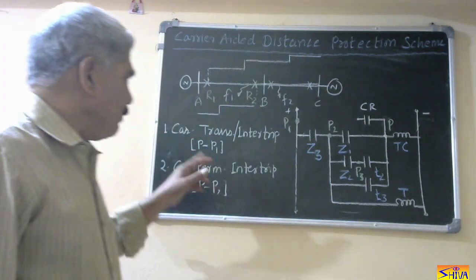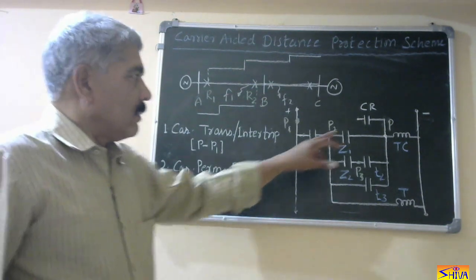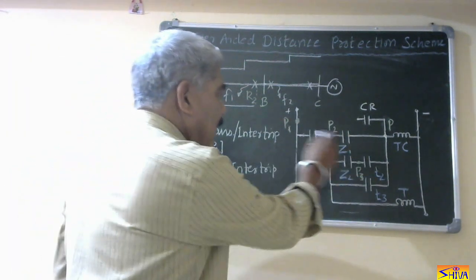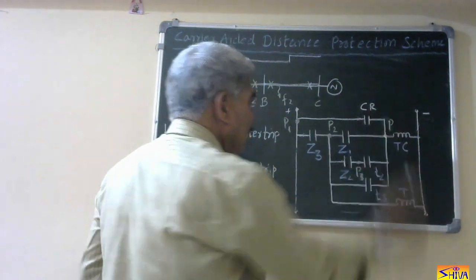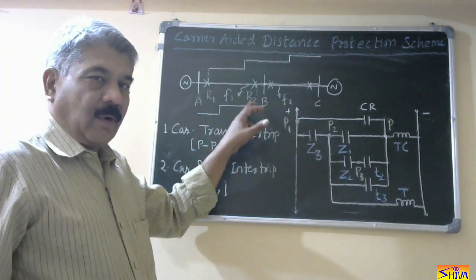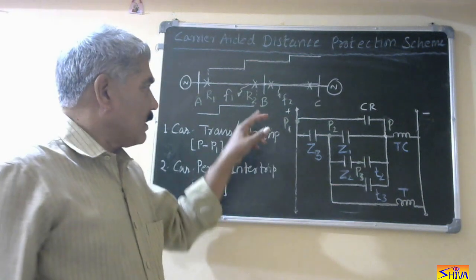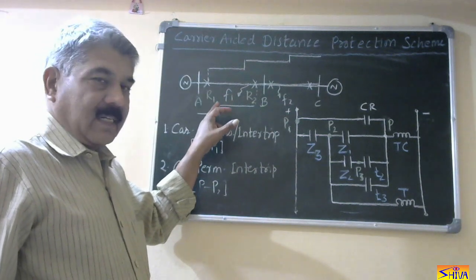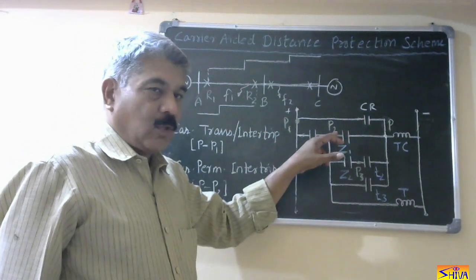Let us start with the first scheme — carrier transfer or carrier intertrip scheme. In this scheme, the carrier receive relay contact, which is normally open, is connected at point P, between point P and P1. When fault F1 occurs — that is, the fault occurs in the second step and it is an internal fault — the local end relay R2 will transfer a carrier signal to R1 so that the carrier receive relay immediately closes its contact.